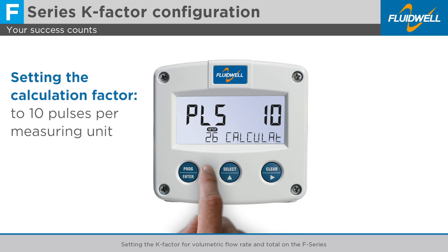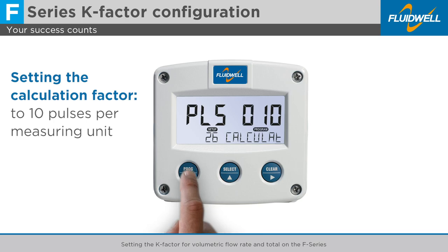Press Select to go to Menu 26, Calculate. Press Prog to change this setting. The flow rate is calculated by measuring the time between a number of pulses. The more pulses, the more accurate the flow rate will be, but also the response time will increase. We are going to select 10 pulses. Press Prog to store the flow rate calculation to 10 pulses per measuring unit.